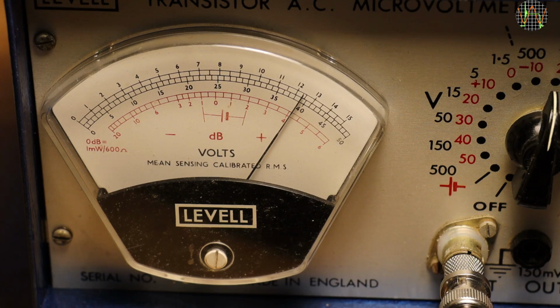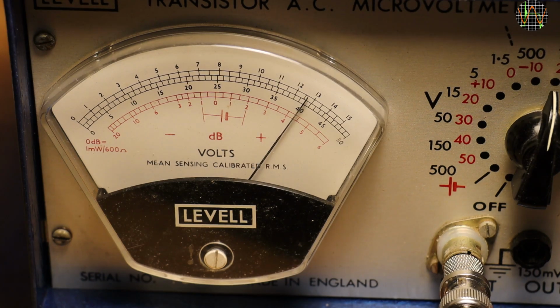And since the only range suitable for this is the 150 millivolt range, I adjust the meter here with a trim pot meant for the 50 millivolts and lower range. Adjusting the wrong pot did however change the needle position because, as the manual states, the low range adjustments do influence the higher ones, which is why they needed to be done first.